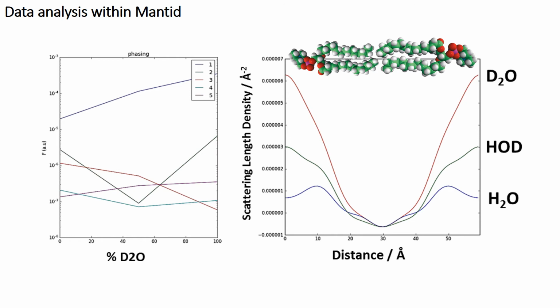Okay, it's a little rough around the edges compared to other stuff that's published, but we're able to identify our lipid head groups, our interbilayer water, our methyl groups, and our aliphatic chains. And so we're able to show, even in its current configuration, CRISP can actually undertake this kind of study with the advantage of being a white beam instrument and having a horizontal geometry.